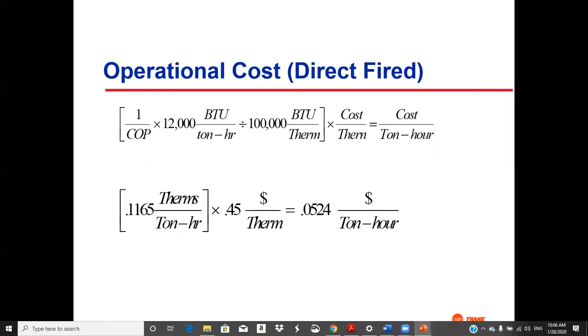The useful energy, if we're doing this per ton hour, is 12,000 BTUs per hour. That's by definition a ton hour. So I've got cost over useful, and useful cancels out. I get cost, and that's going to be in terms of BTUs. Then I divide by 100,000, and that turns it into therms, because a therm is 100,000 BTUs. Then I multiply by the cost per therm, and that's the cost to get a ton-hour of refrigeration. It's good to think your way through that and make sure that you really understand what the calculation is.